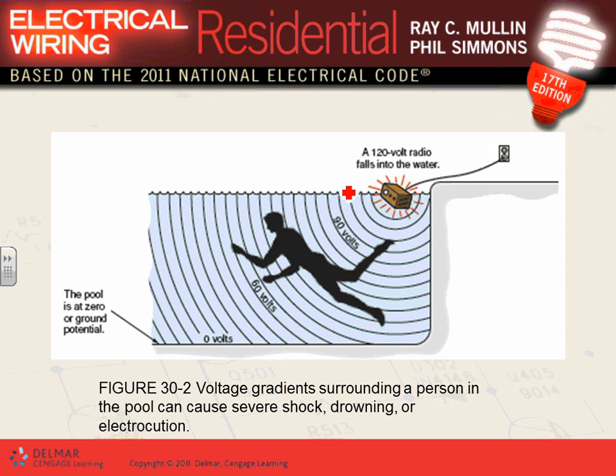Voltage gradients, guys. I don't know if you're familiar with this concept. If you drop something energized in a swimming pool, or a spa, or a hot tub, you know what happens? The electricity will go through the water. If you drop a radio, stereo, or something, electricity will go through the water and create different voltage levels. Look at this. So this is sitting at different voltage levels. That's called the gradients, all the way to 0 level. The further away you go from the point where you drop it in the water, the more the voltage goes to 0 level.